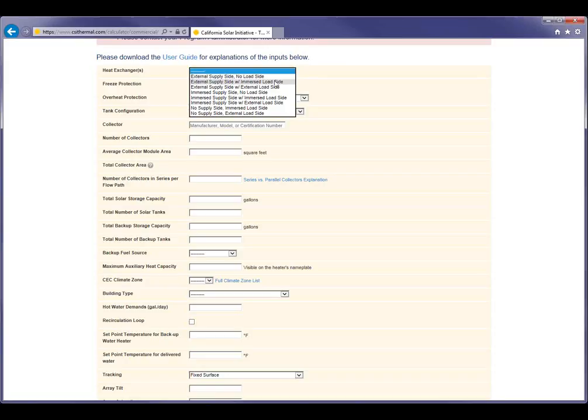And those heat exchangers can be external to a tank, or they can be immersed in a tank, like in the diagram that Steve showed on how solar thermal works, that had an immersed coil within a tank. So we really need to specify whether the heat exchanger is on the supply side, the load side, both, and is it an external heat exchanger or an immersed heat exchanger. So if we follow the example in that earlier slide with the coil in the tank, that would be an immersed supply side heat exchanger, where that collector heat exchange fluid is coming directly through the coil on the bottom of the tank. So I'll go ahead and select that option for now.